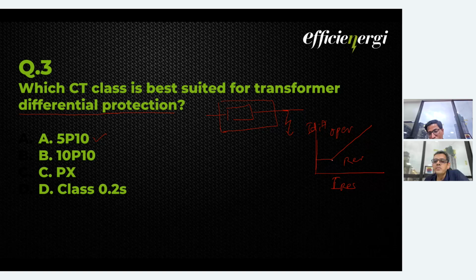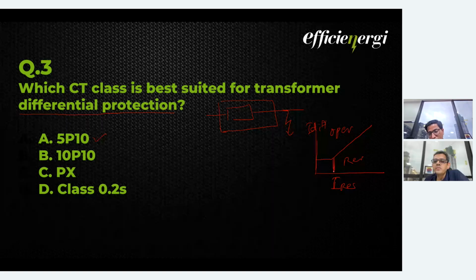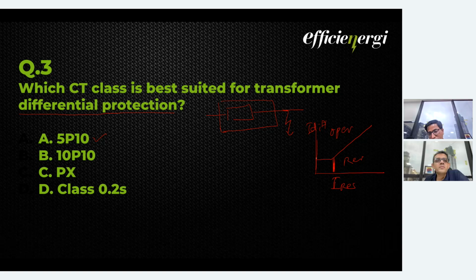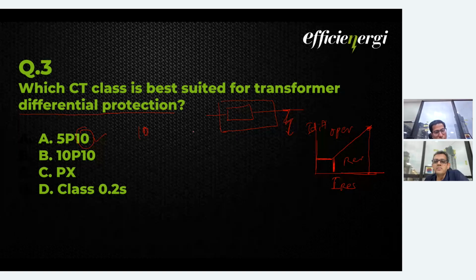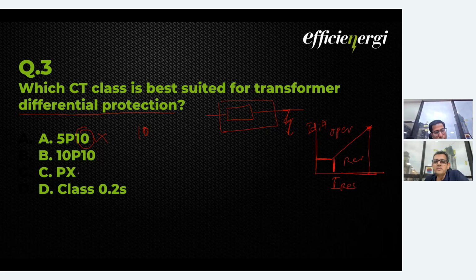So if you see at lower currents, that is for internal faults, the differential magnitude is very low. But as the fault goes higher, the differential becomes high. So it is expected that for an external heavy fault it should not operate, but for an internal small fault it should operate. So here the P10 means, as I told, 10 times the primary, it will not saturate. So for this particular differential protection, these CTs are not suitable. We have to go for a PX CT.